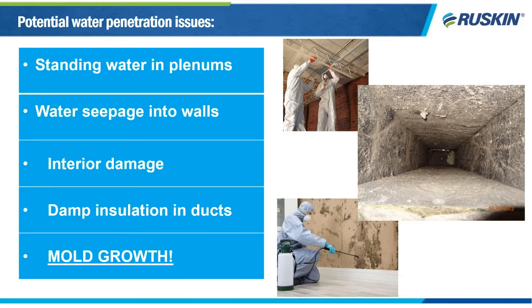And we all know that rain blowing into your building can cause a lot of trouble. Generally, standing water in plenums and ductwork often leads to water seepage inside walls and past. Wind-driven rain can travel several feet into an open mechanical room, making wet floors and equipment, and it can travel down ductwork, soaking your liner and causing problems there. Damage to interior things such as drywall and ceiling tiles is common too. Even the best designed and fabricated sheet metal ductwork has the ability to leak if water stands in it.